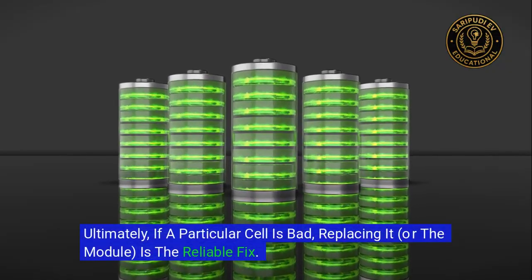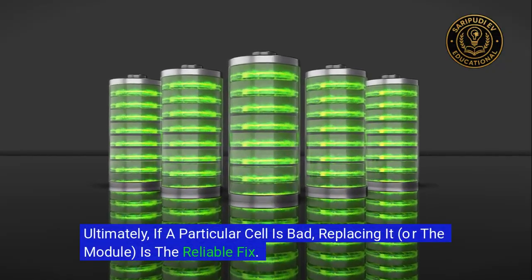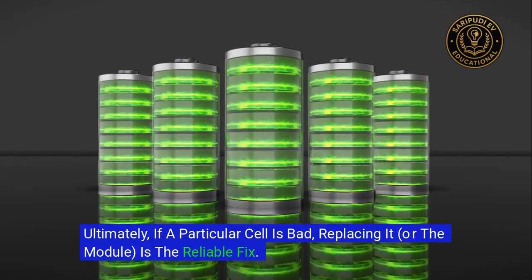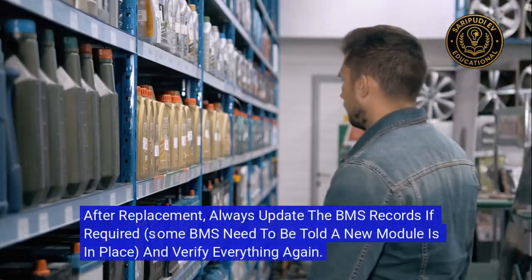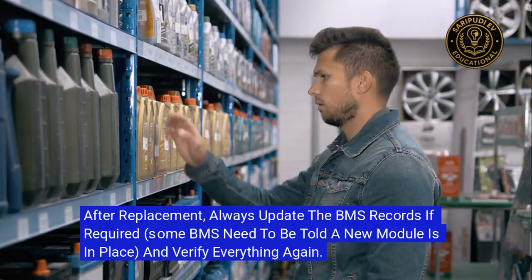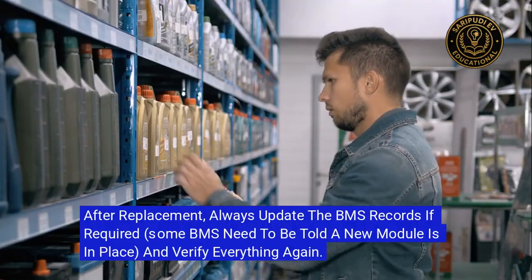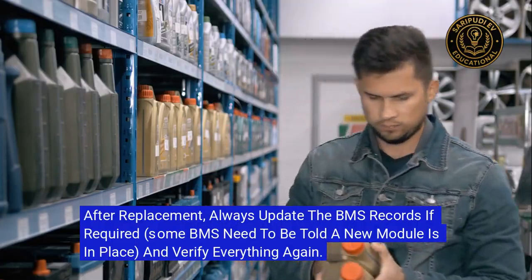Ultimately, if a particular cell is bad, replacing it, or the module, is the reliable fix. After replacement, always update the BMS records if required. Some BMS need to be told a new module is in place, and verify everything again.